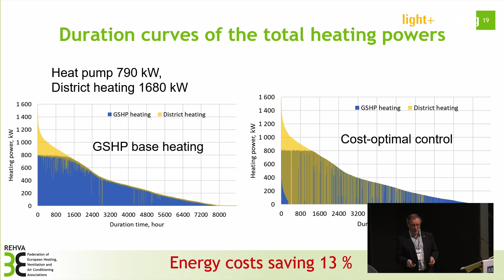This is based on the electricity price and also the COP of the heat pump. Looking at the other duration curve, we can see that almost all through the heating season there are some hours where it makes sense to use district heating instead of the heat pump. This means that for this case, the energy cost saving is about 13% with this more modern control optimization system.